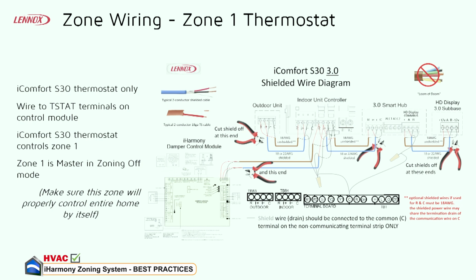So your R and C, your 24 volts, will be in a run of 2 conductor conventional thermostat wire, and then your I plus and I minus will be in a 2 conductor shielded. That's the best way to prevent issues with these, is shielded wire. Or bare minimum, again, talking about the site visit I told you about before, where they had 8 wire run for everything. And again, they're just getting beat over the head with communication issues.